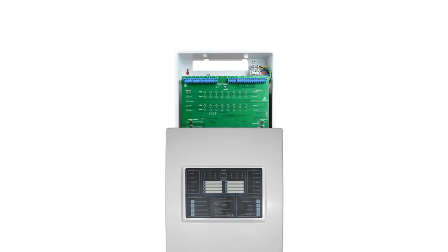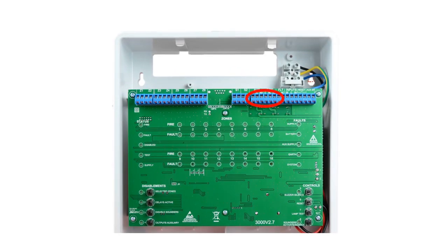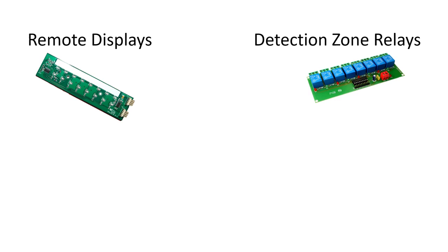Inside the panel, there are terminals to connect wiring for alarm and fault outputs, an auxiliary 24-volt supply output, and inputs to initiate day-night mode, building evacuation, and a system reset, all from remote locations. Apart from the panel configuration options, there are also additional hardware options available. A remote LED card allows the alarm and fault status at the panel to be monitored from another location. Each detection zone may be mapped to an output relay, allowing for other events to be initiated, like shutting down air handling plant when a specific detection zone reports a fire.